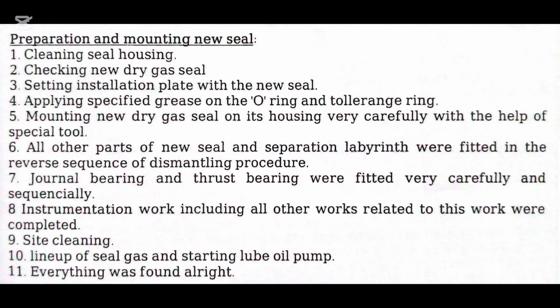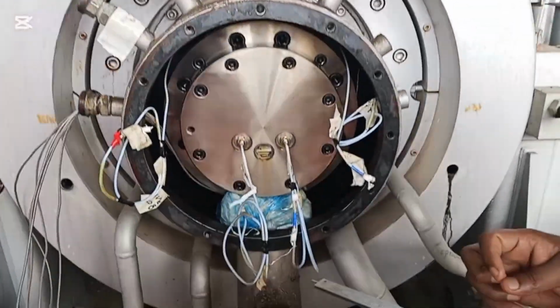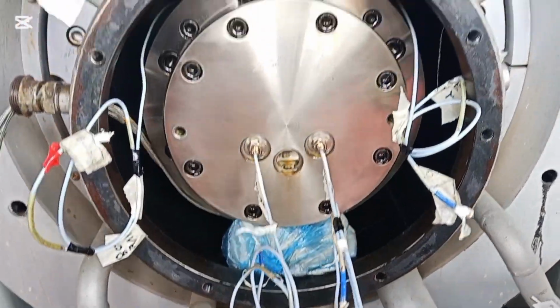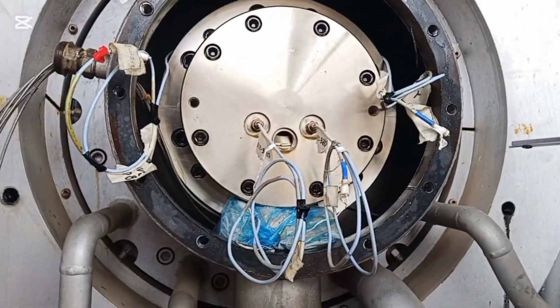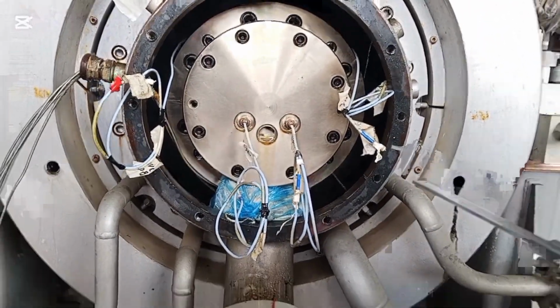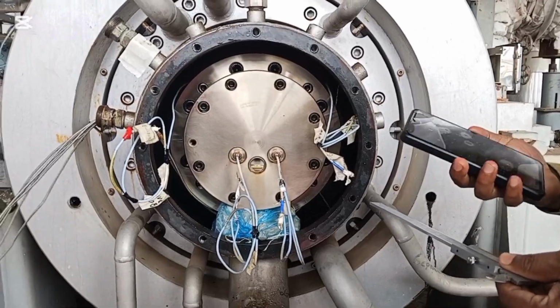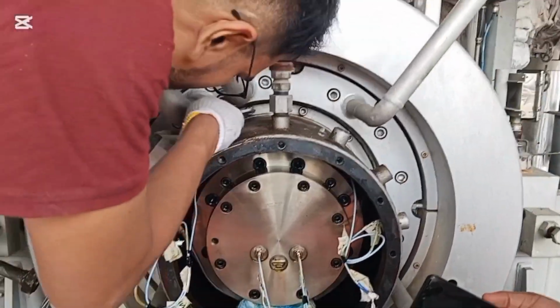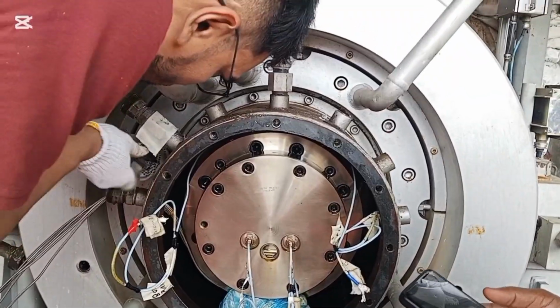water content in the nitrogen line, and we found that from our power plant there are two valves connected with the steam line as well as the nitrogen line. When the power plant is in shutdown condition, nitrogen flow is needed, and we found the valve was maybe somewhat loosened, so we tightened the valve, and also we drained the moisture content. Finally we came to a decision that from this position maybe condensate entered into the nitrogen line.